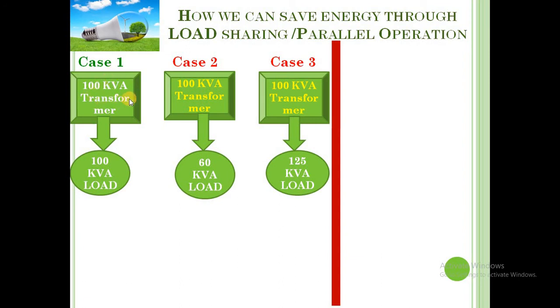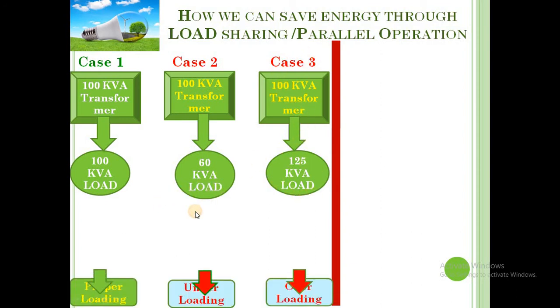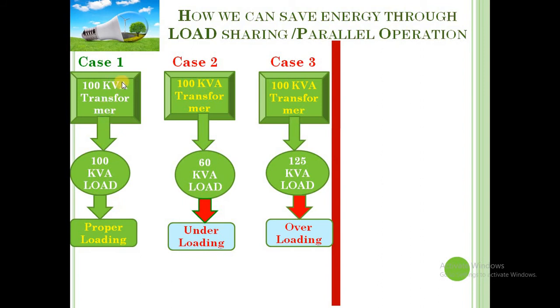So in the first case, a 100 kVA transformer is used to supply a 100 kVA load. In case 2, the 100 kVA transformer supplies a 60 kVA load, meaning the load is only 60 kVA and the transformer is of 100 kVA. And in the third case, a 100 kVA transformer is used and the load is 125 kVA, that is 25 kVA is the extra load in case number 3. Now what will happen? In the first case, a 100 kVA load is there, hence the 100 kVA transformer we have used will have proper loading.